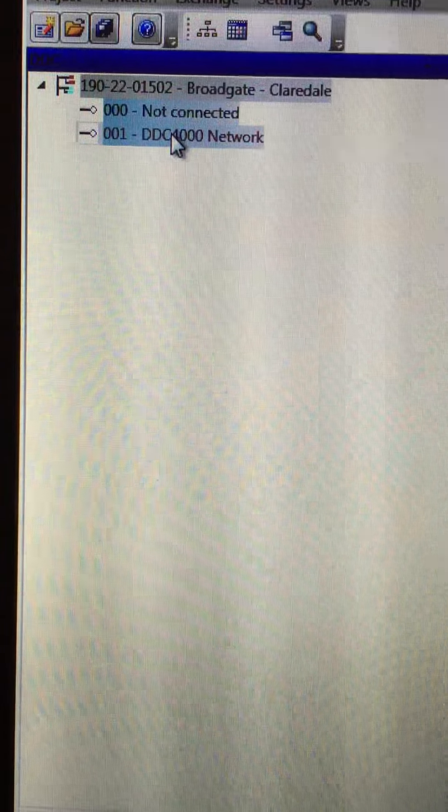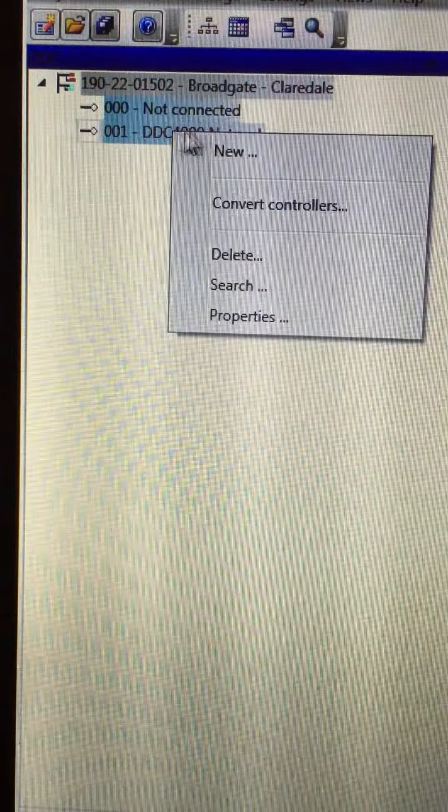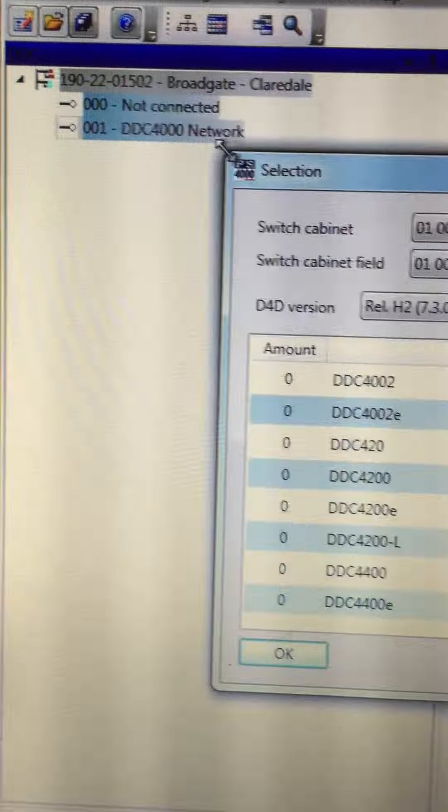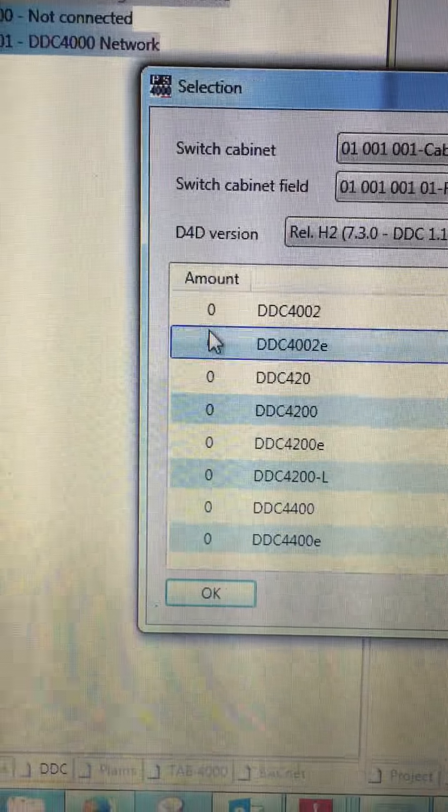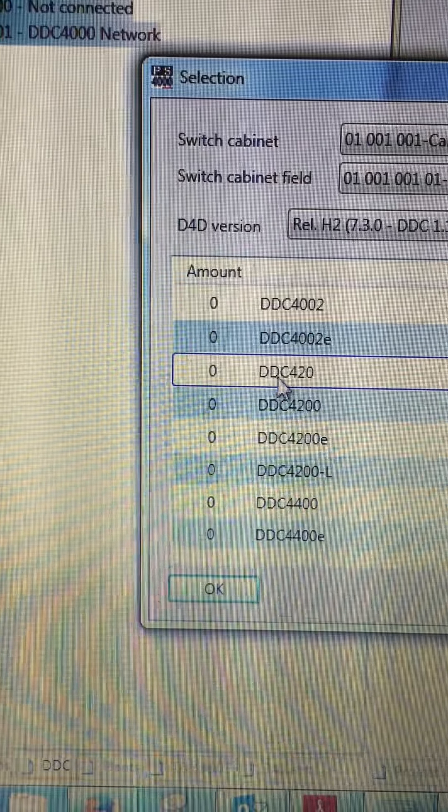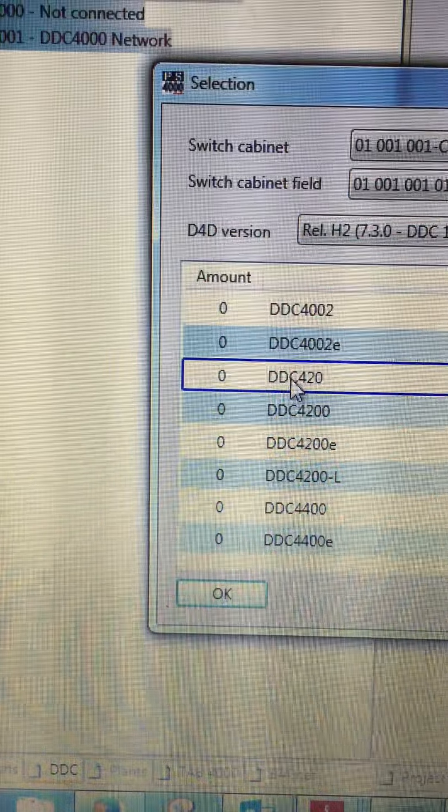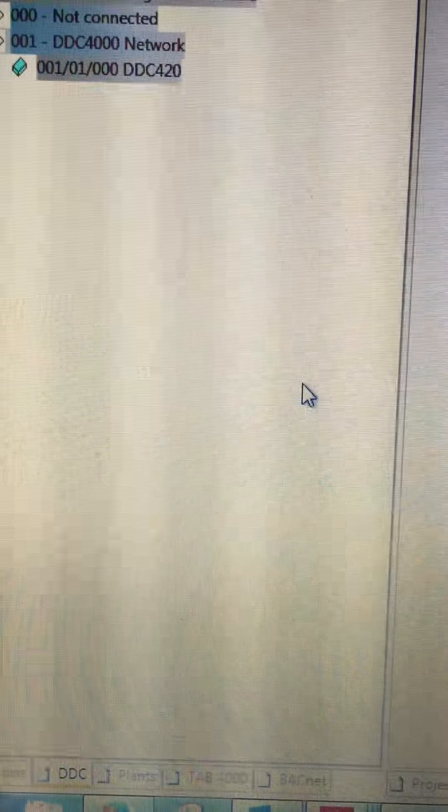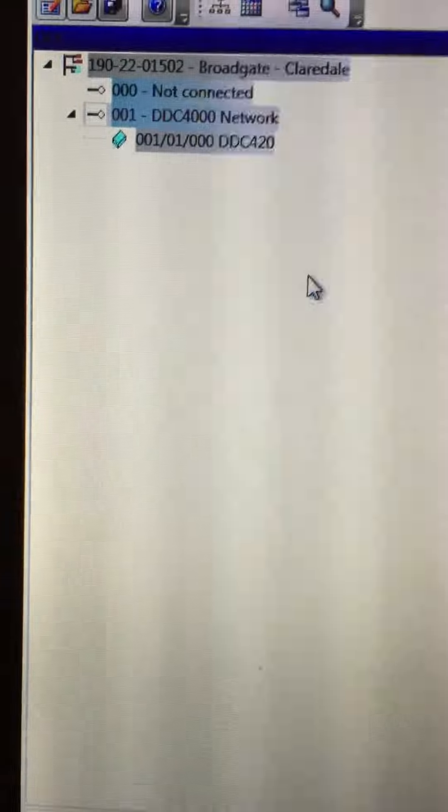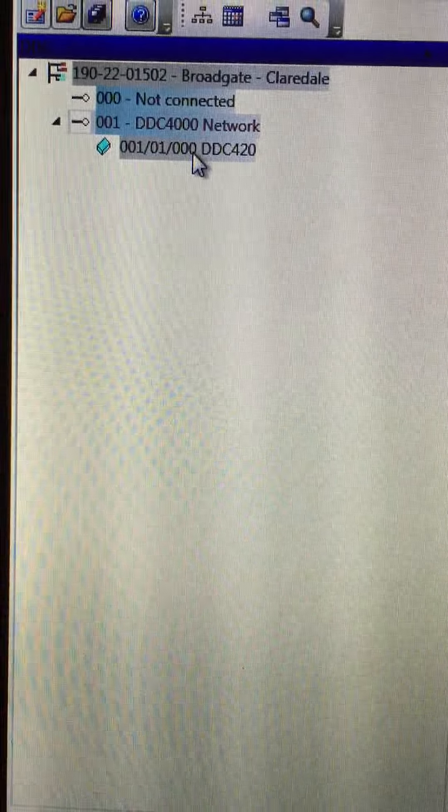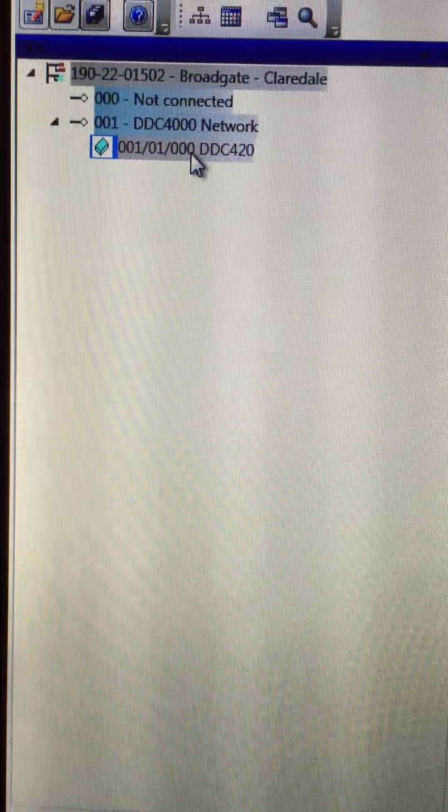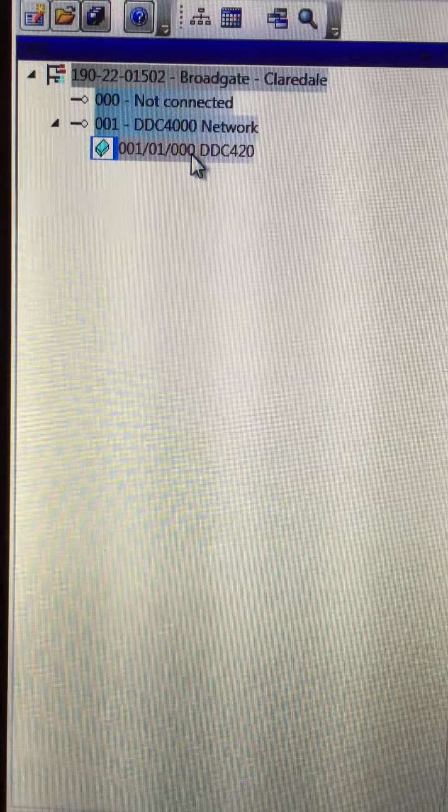So the first thing we need to do is to access the DDC tab and then introduce a DDC4000 network. We introduce the controller by right clicking on the network and select new and then choose DDC420. Just double click to get one controller and now I right click and look at the properties of that device.